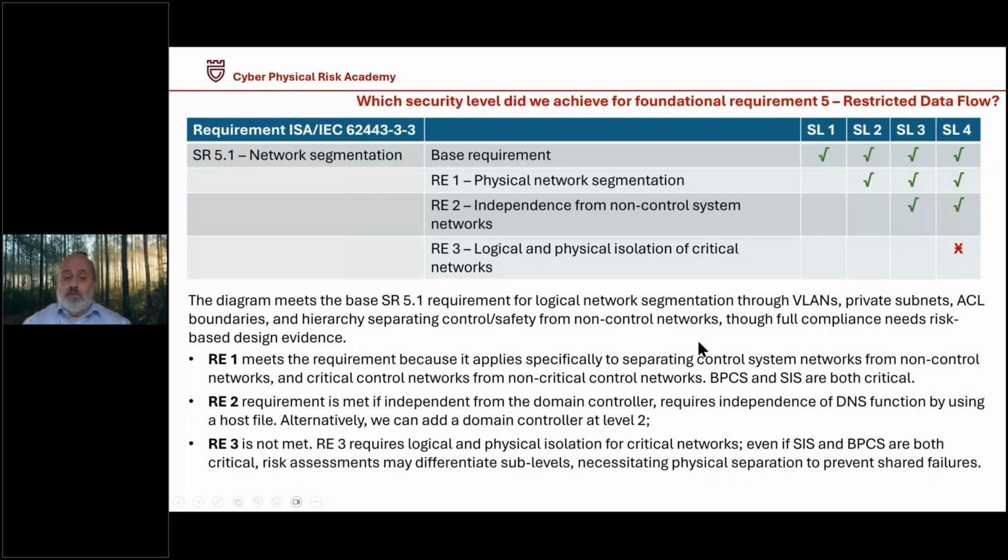It requires a logical and physical isolation of the critical network, and it requires physical separation to prevent shared failures. So I cannot meet that with my VLAN split zone. I would really need an extra switch pair to do that.